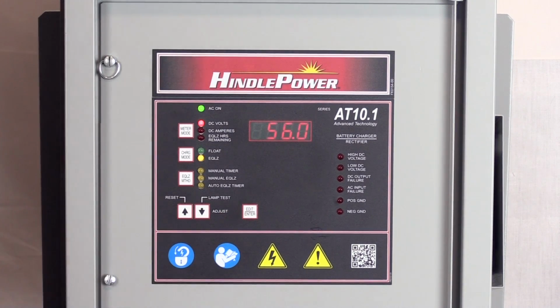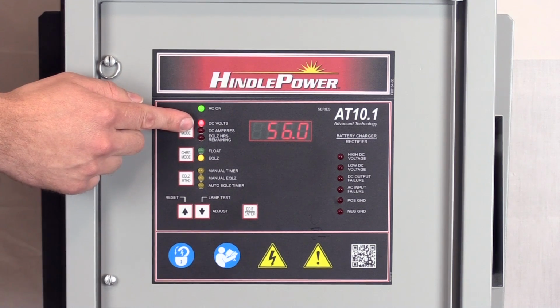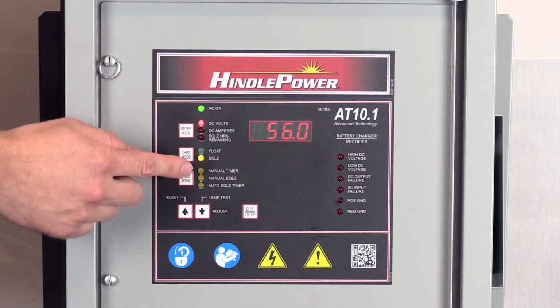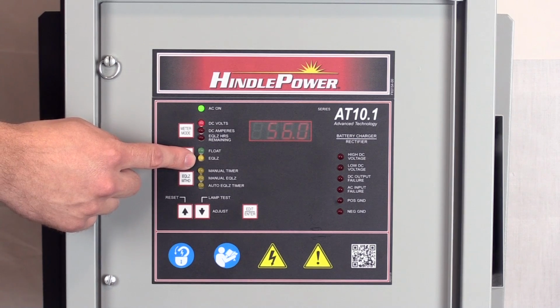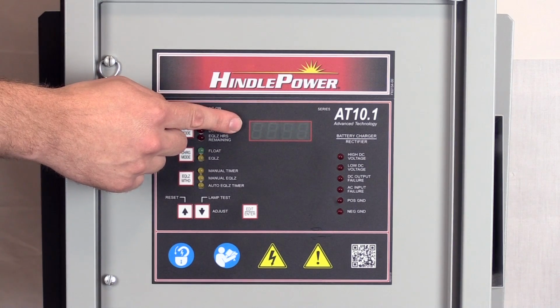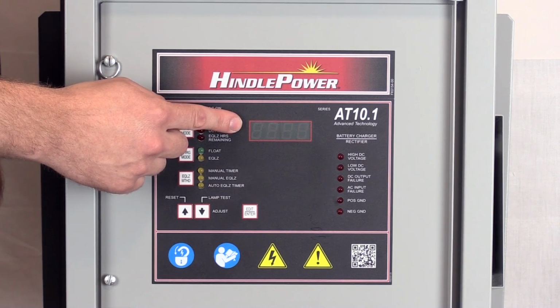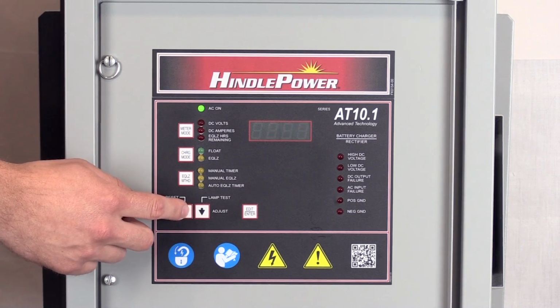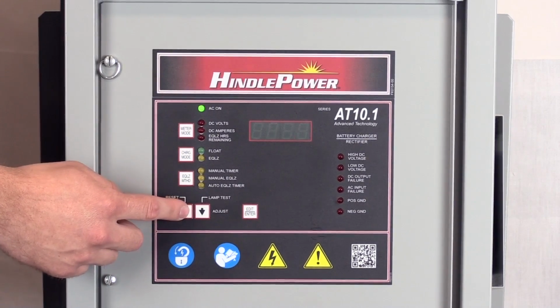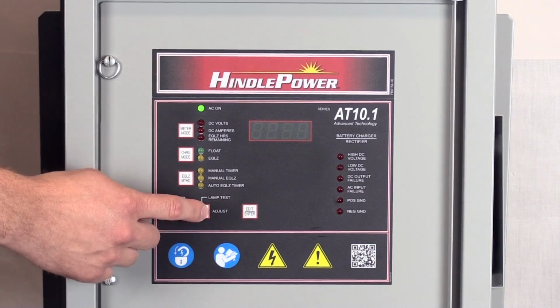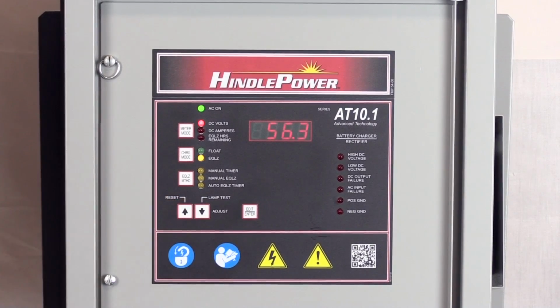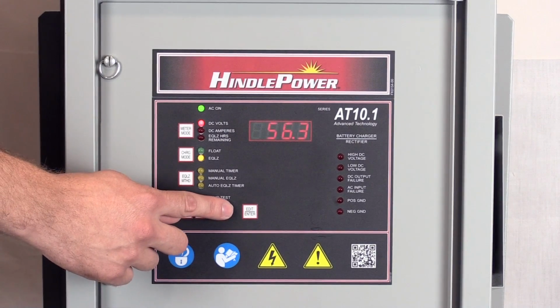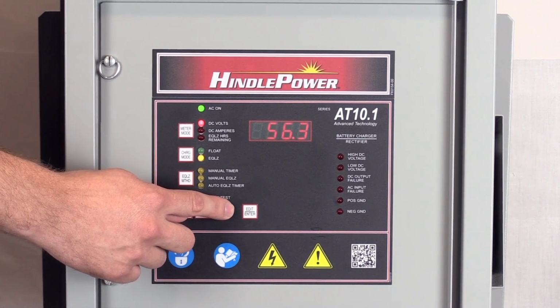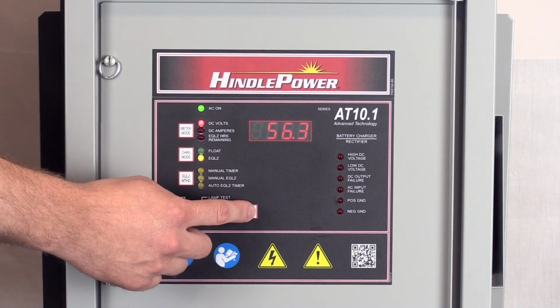The next parameter is the equalize voltage. The red DC volts LED will flash, the yellow equalize LED will flash, and the LED display will flash the equalized voltage. Press the up and down arrow keys to adjust the set point. Press the Edit Enter key and this will save your changes and go on to the next parameter.